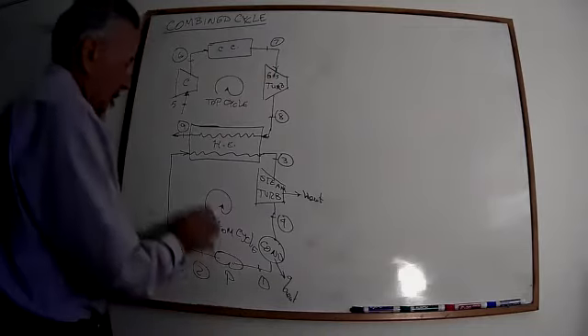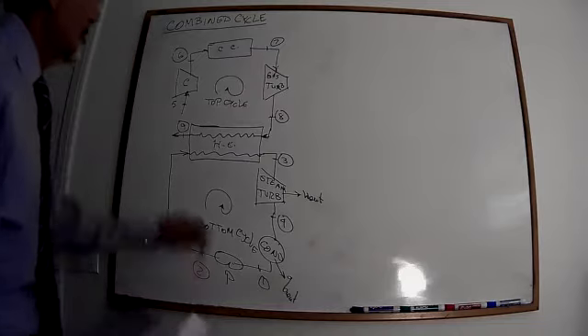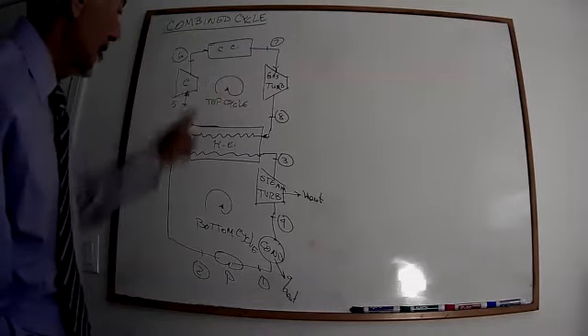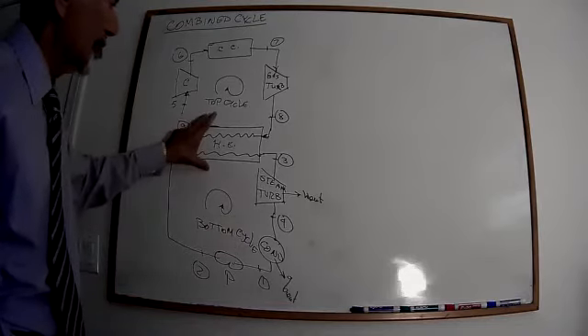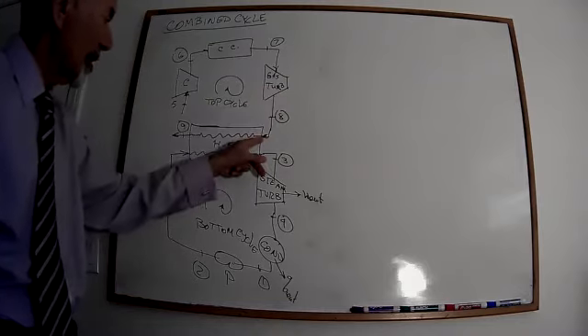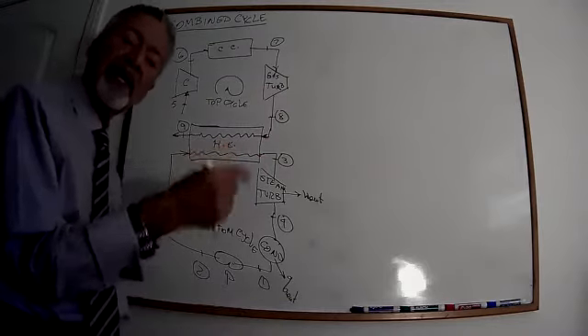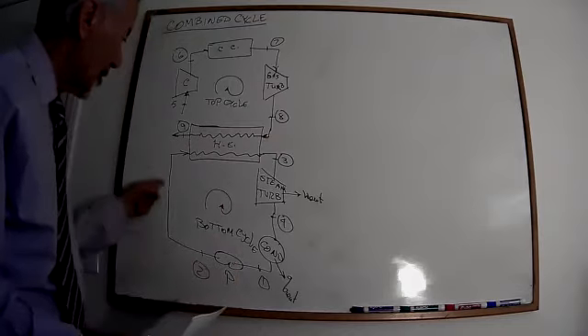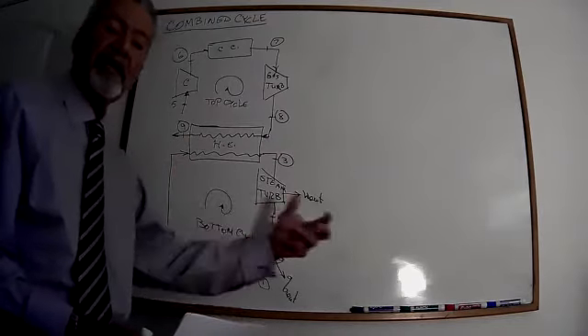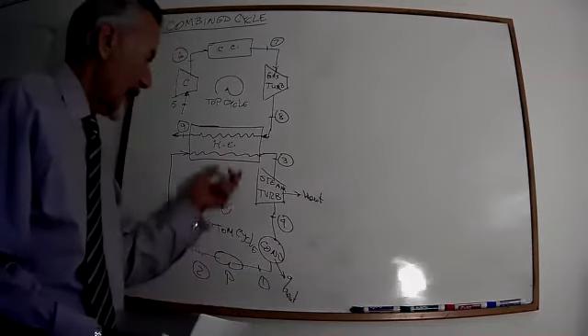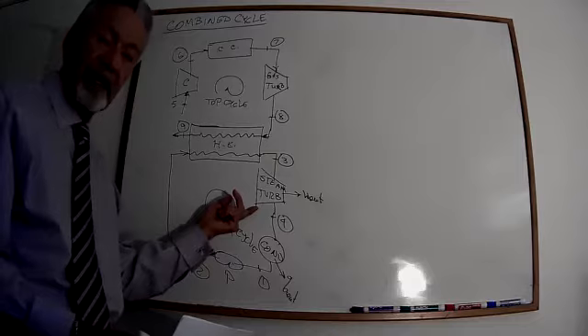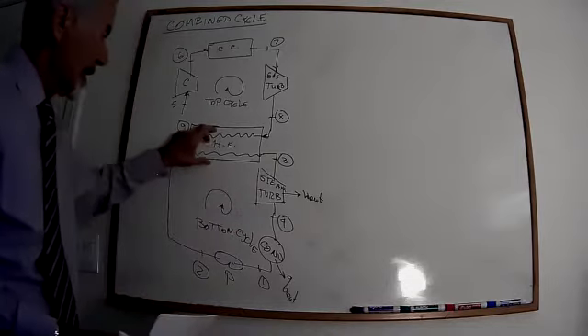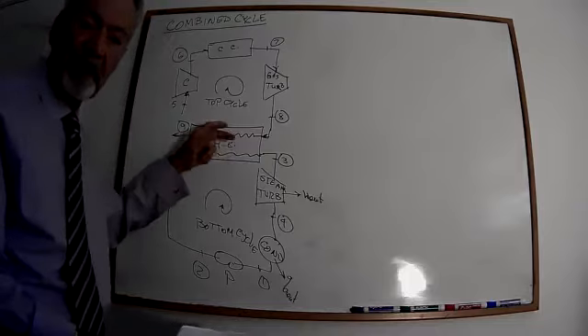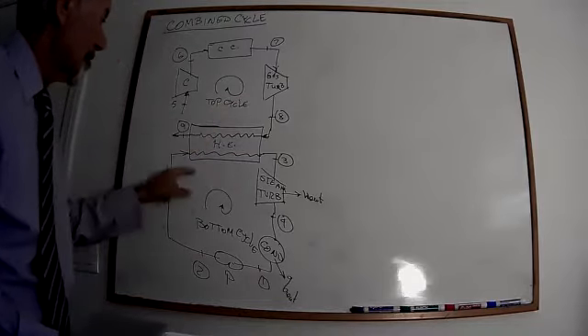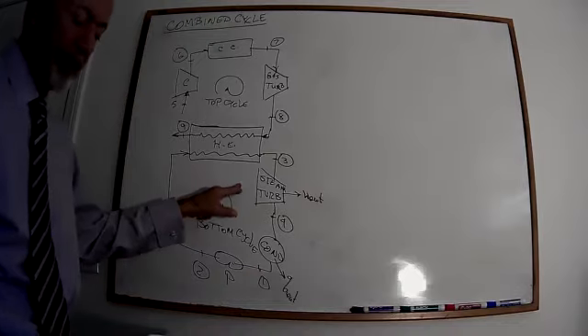Now, since this is two separate cycles, this cycle's working fluid is air, this cycle's working fluid is water. As you can see, they never get mixed with each other. The hot gas coming out of the turbine goes inside the tube of the heat exchanger. The water flows over the tube, gains heat from the surface of those tubes, and then becomes steam and runs the steam turbine. That's the whole concept. The net energy within this heat exchanger is zero—whatever comes out there will be gained by the bottom cycle.